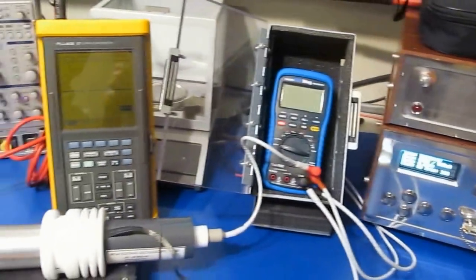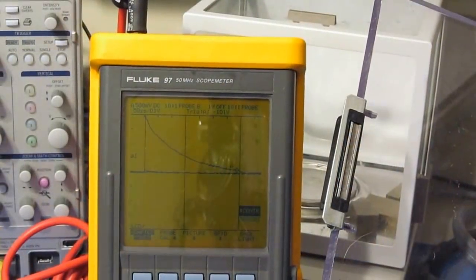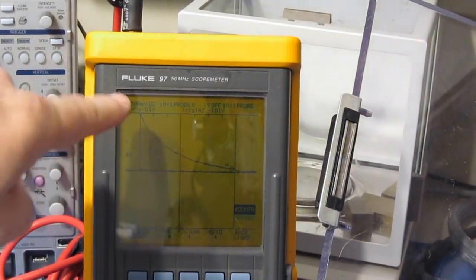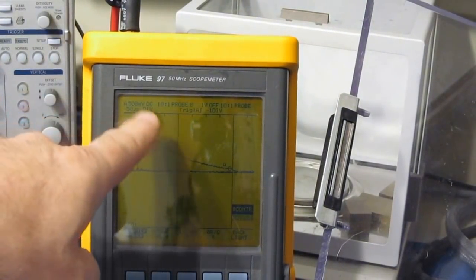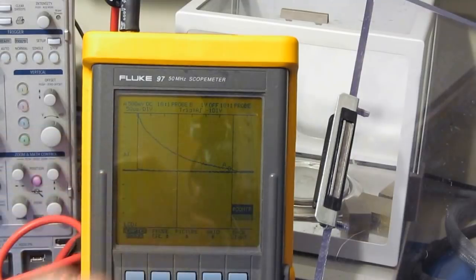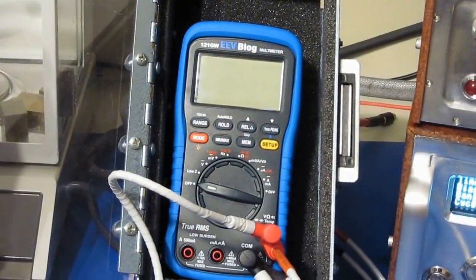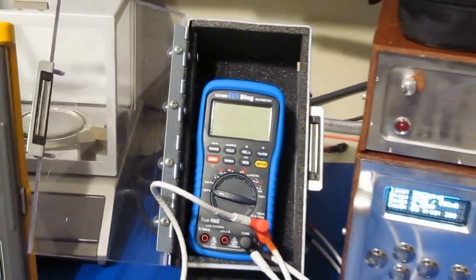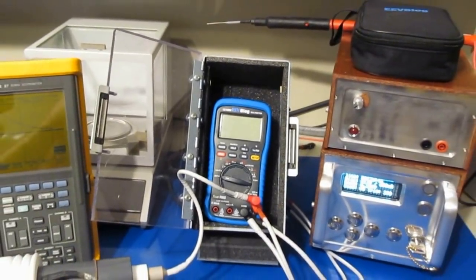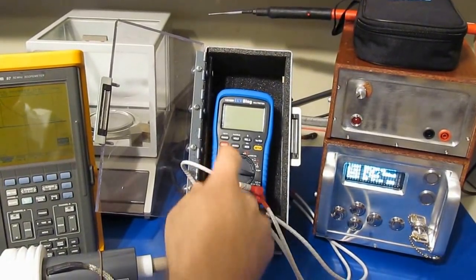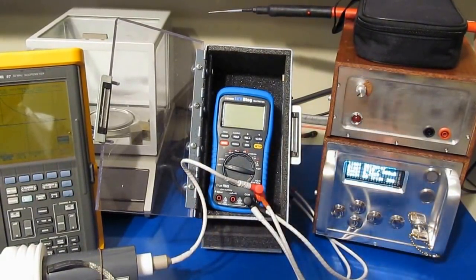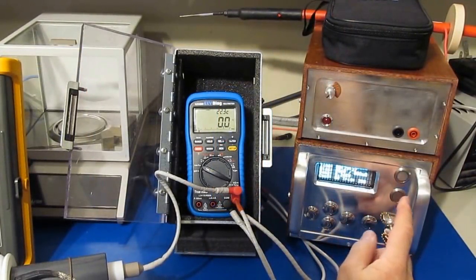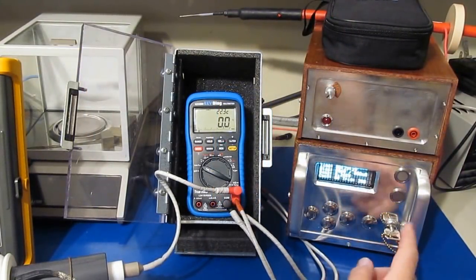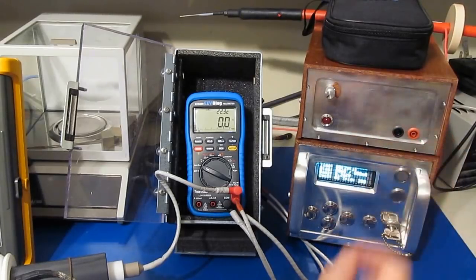So I've reprogrammed our generator. Boy, the glare is just terrible off the scope. So you can see we're 4 divisions up at 500 volts per division, so 2000 volts. Again, this is a 100 microsecond full width half height with a 2 ohm source impedance. So this is where the meter had failed previously. So again, we'll be repeating the same test. This will be 5 transients, positive and negative, in each mode of the meter.